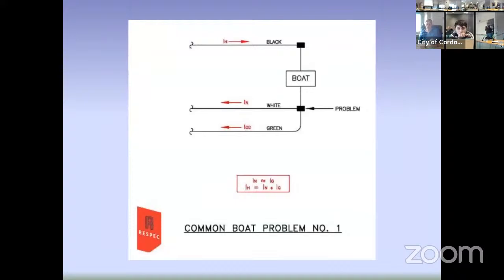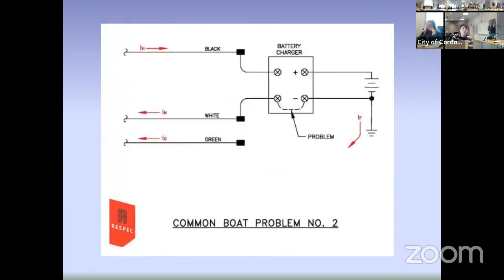Yeah, these are the three examples that I talked about earlier. So if the ground is tied into the neutral on the boat, that will create a problem. What happens is the current coming through the load on the boat will get split between the neutral conductor and the ground conductor, and then we'll have a positive value on the ground fault relay, and it'll trip. Let's go to the next one. This is the one I talked about. And just to point out here, we're showing the ground conductor, the green conductor, separate from the white conductor, which is the neutral. And that's what we should have on the boat.